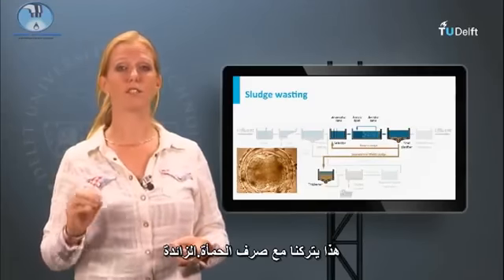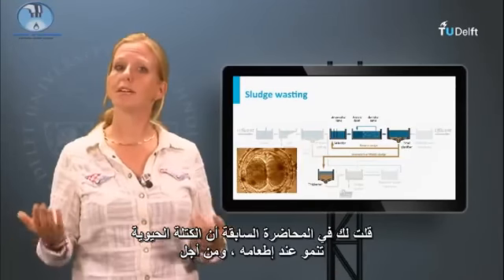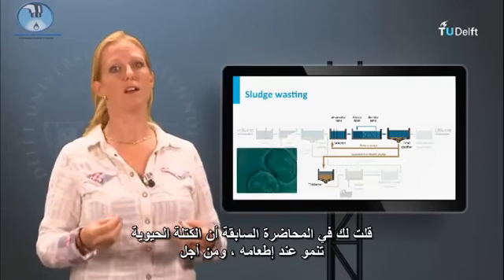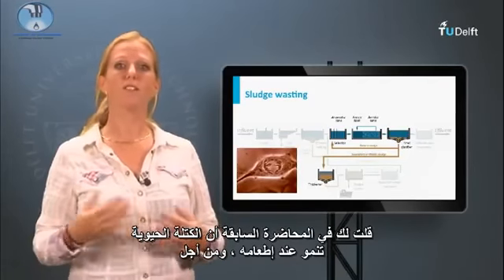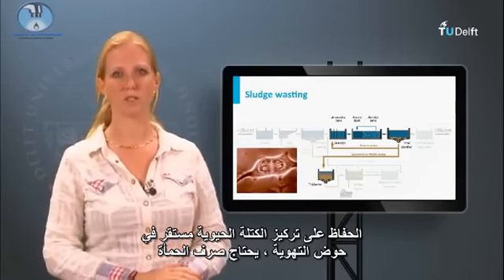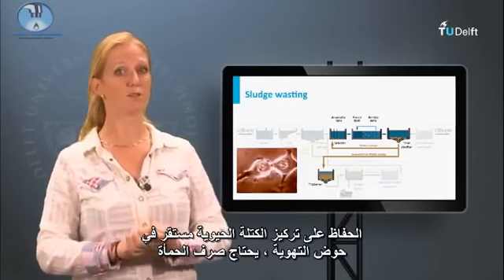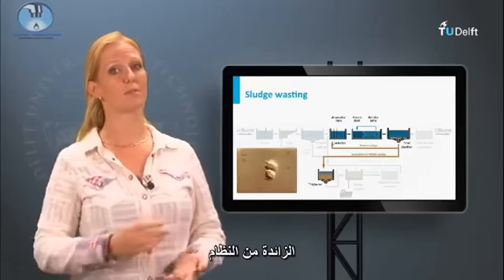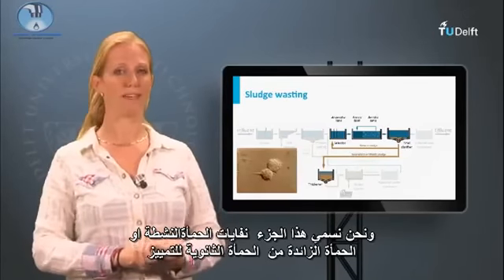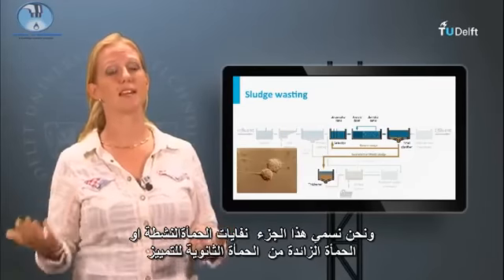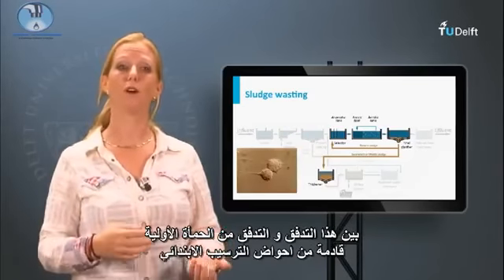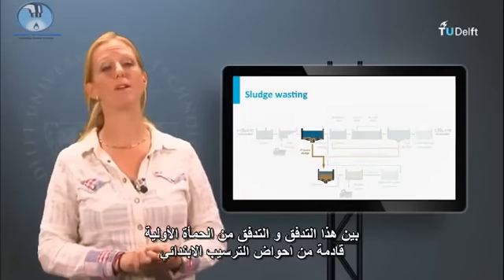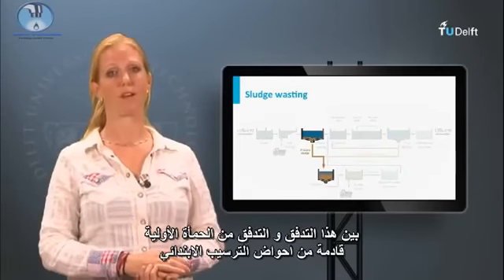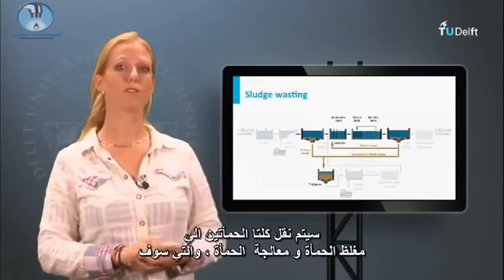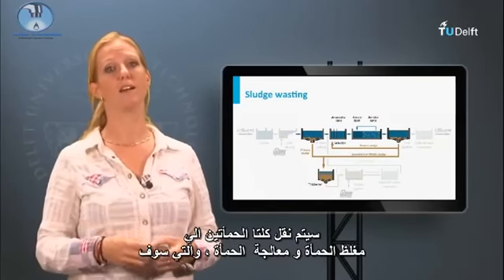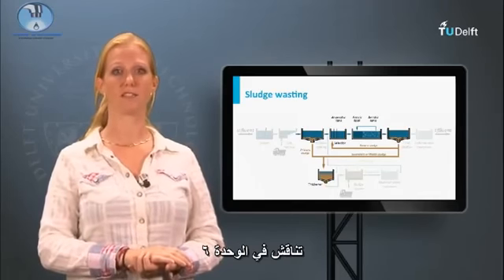This leaves us with the sludge wasting. I told you in the previous lecture that biomass grows when you feed it. So in order to keep a stable biomass concentration in the aeration tank, the sludge growth needs to be removed from the system. We call this fraction the waste activated sludge or excess secondary sludge to distinguish this flow from the primary sludge coming from the primary settler. The 2 sludges will be transported to the thickener and sludge handling, which will be discussed in Module 6.